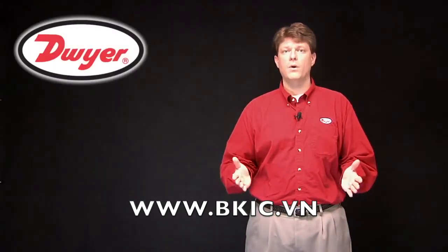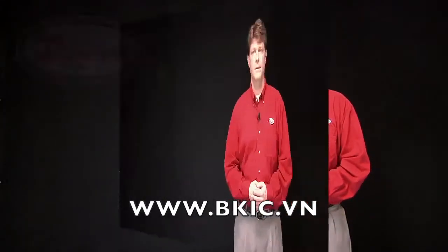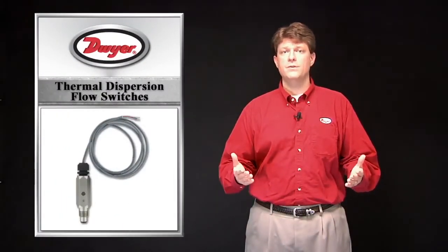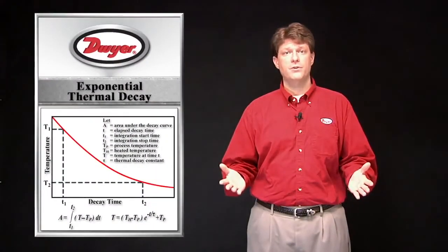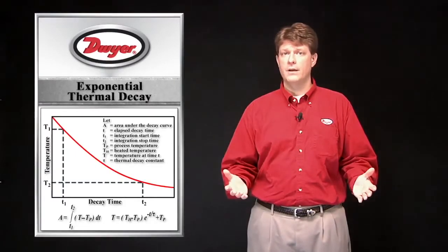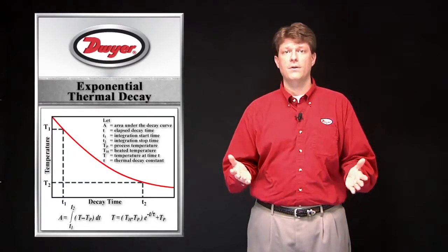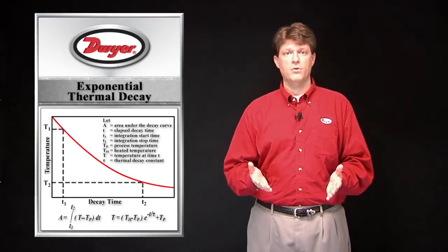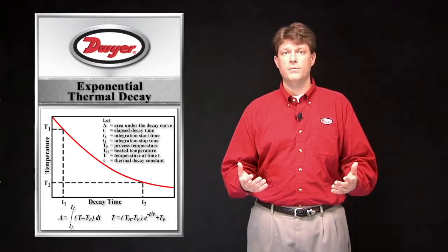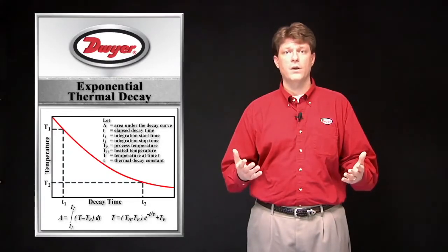In this video I will cover thermal dispersion flow switches. Dwyer Instruments offers several flow measuring products that use a thermal sensing element. Thermal dispersion flow sensors use a temperature element that is heated up beyond the media temperature. Based on calorimetry, the flow moving past the sensor will have a cooling effect that is directly proportional to the flow velocity.